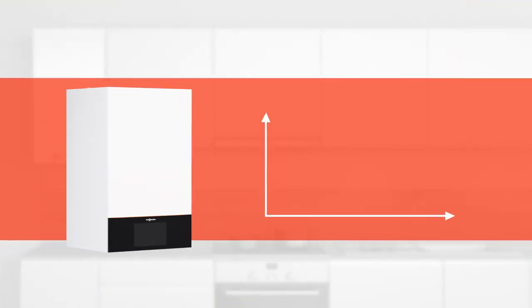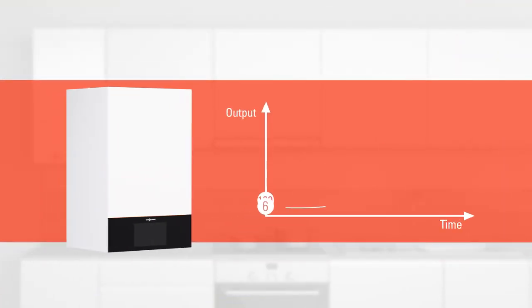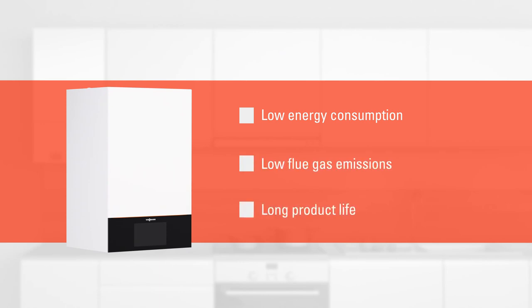When you need less heat, this boiler is able to modulate its heat output down to 6% of the maximum. Even when it only uses a small amount of its output, the boiler can be operated continuously and avoids frequent starting and stopping. This enables energy-saving operation, low emissions, but above all, a longer life.